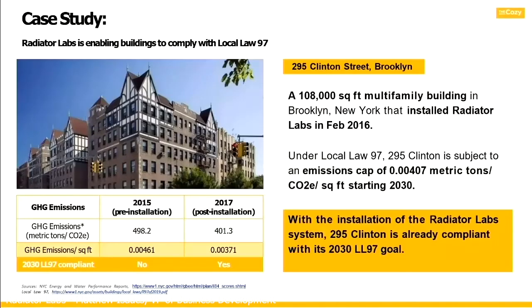This is an example - the same building that we looked at on the slide with all those columns. It's a LeFrak building, it's 100,000 square feet, it's in Brooklyn, it's a single pipe steam building. It's actually the most efficient single pipe steam building in New York City, and it's already compliant with Local Law 97 2030 guidelines with the simple addition of insulating the pipes and adding cozies to the radiators.